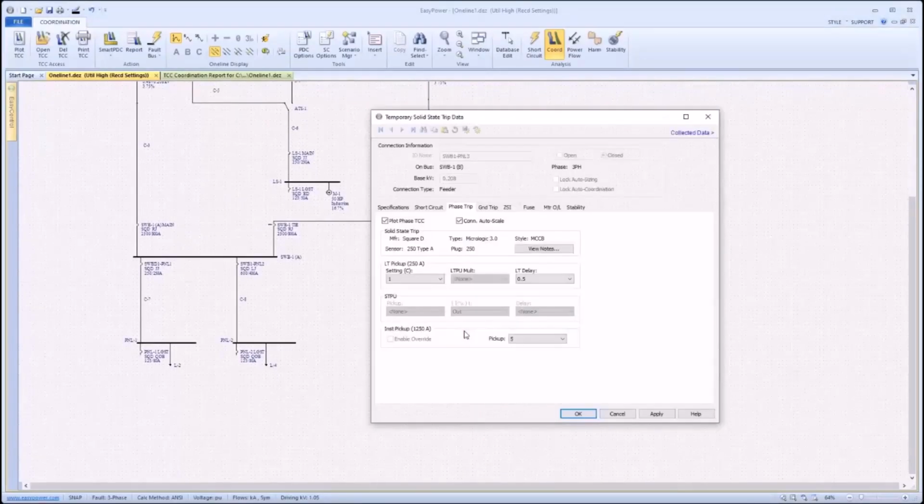It was to raise the instantaneous from, I believe it was on minimum, to 5. So any change I make in the base case, I could set that instantaneous to 7 or 3 or whatever it might be, and that will not overwrite the changes made in this scenario. Just to be clear, any changes I make here would not overwrite any settings changes that are actually made here.